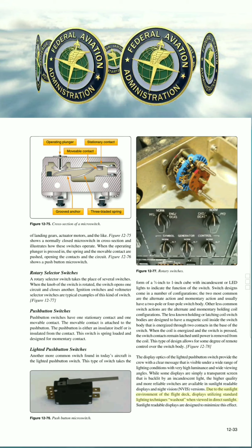The less known holding or latching coil switch bodies are designed to have a magnetic coil inside the switch body that is energized through two contacts in the base of the switch. When the coil is energized and the switch is pressed, the switch contacts remain latched until power is removed from the coil. This type of design allows for some degree of remote control over the switch body. Figure 12-78. The display optics of the lighted push-button switch provide the crew with a clear message that is visible under a wide range of lighting conditions with very high luminance and wide viewing angles.